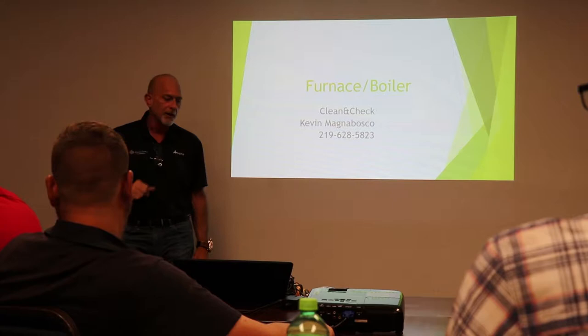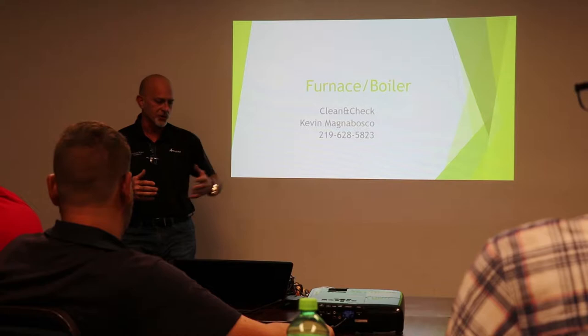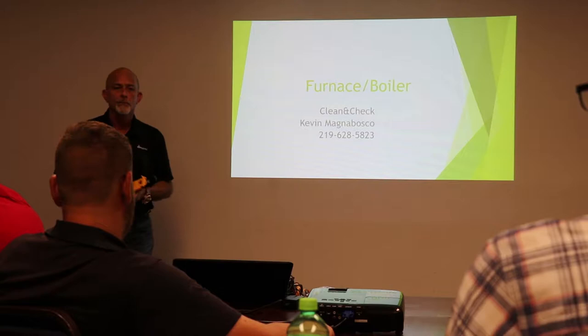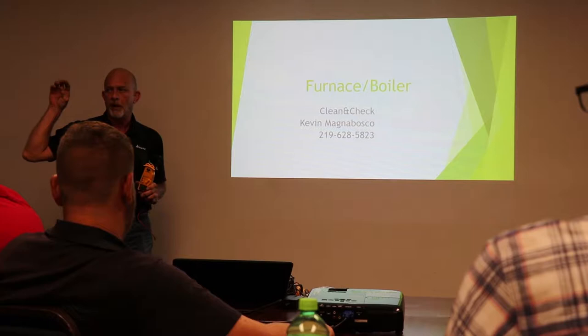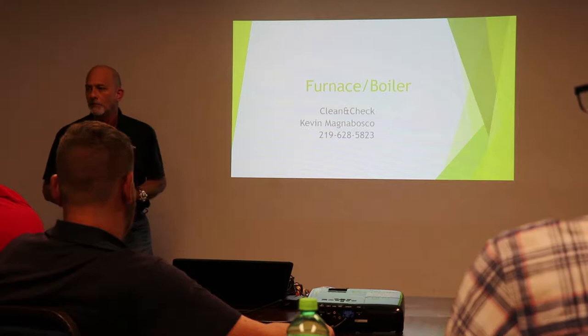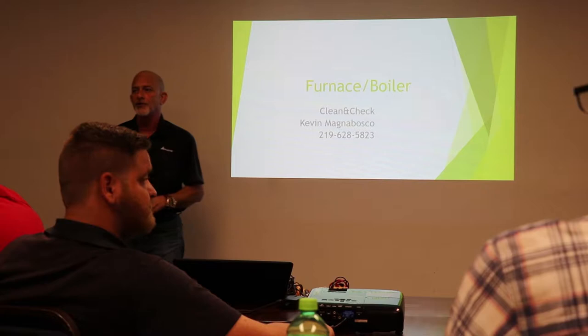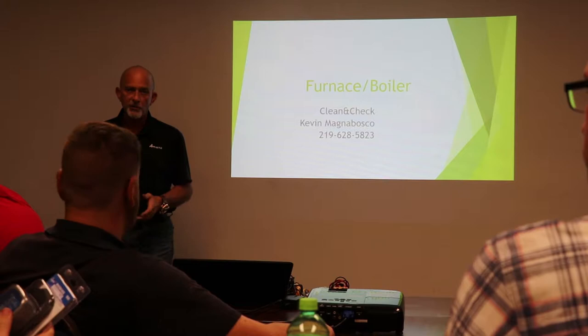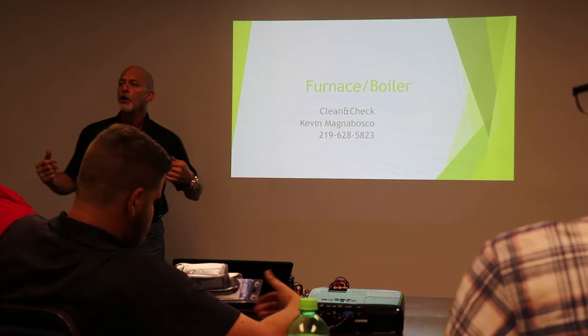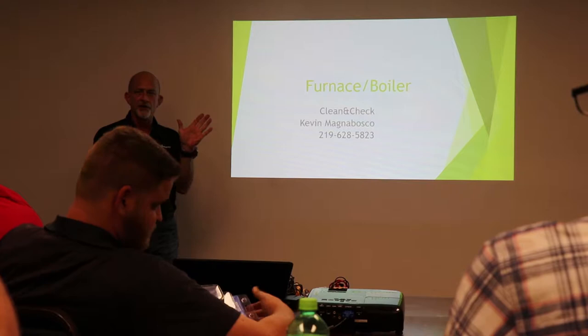That megohmmeter has lights on it. You do have a number value on there as well, but quite honestly, if you go out there with just your meter to ohm out a winding and try to explain that to the customer, they hear blah blah blah. You might as well be speaking Chinese because they have no idea what you're saying. That megohmmeter is done with a series of lights. Pretty simple. If it's good, it'll be a green light. If it's questionable, it's going to be yellow. If that winding is going to go on that compressor, it's going to show red. Homeowners are visual and audio. Simple. They'll understand green, yellow, red.